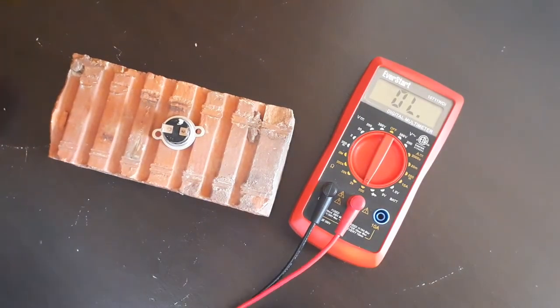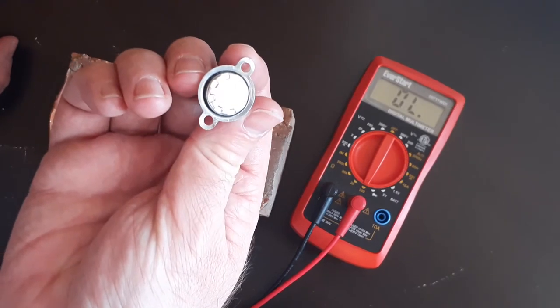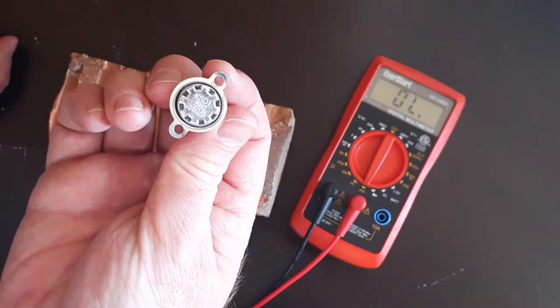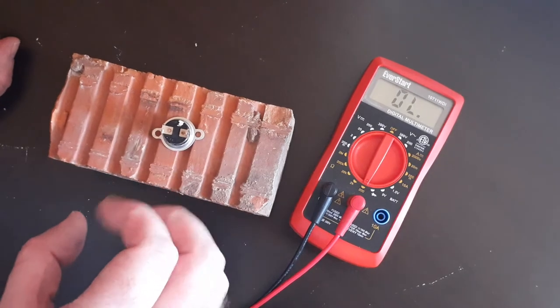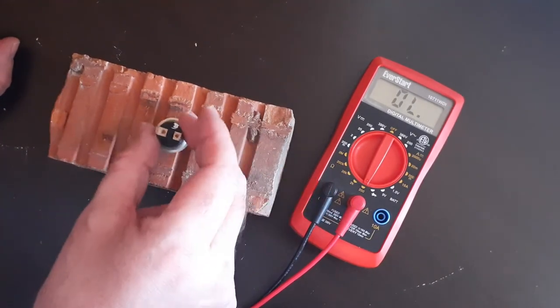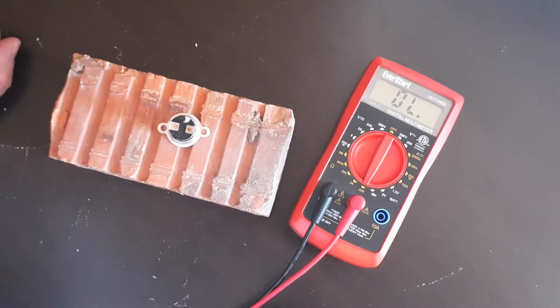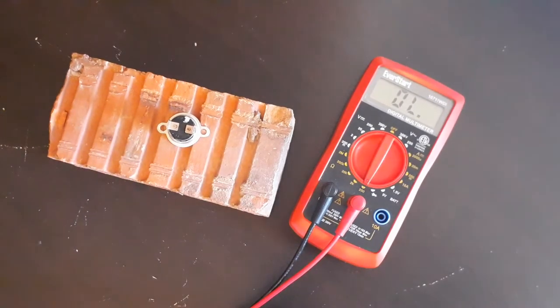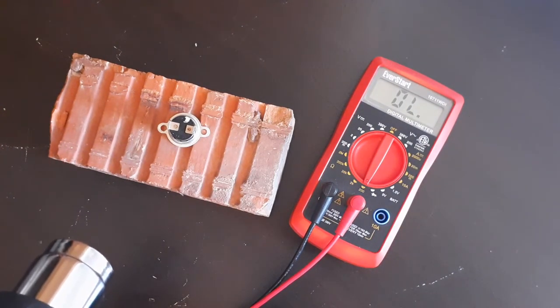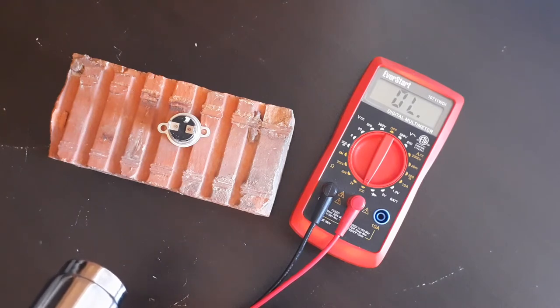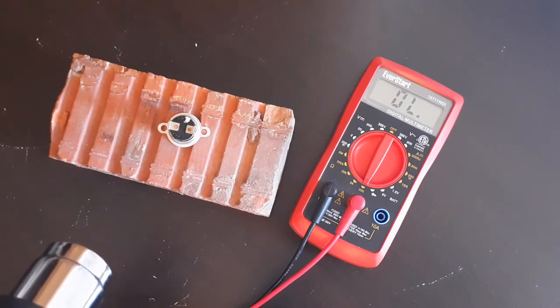Now what we're going to do is we're going to heat this baby up. When it reaches the temperature of whatever's labeled on this—110 degrees—once it reaches 110 degrees from the heat gun, the tabs on the inside are going to open. They're going to pop and open, and this thing should jump and move a little bit when the tabs open. Some of them do, some of them don't. Don't put your heat gun too close or it will start to melt the thermostat's black plastic casing.